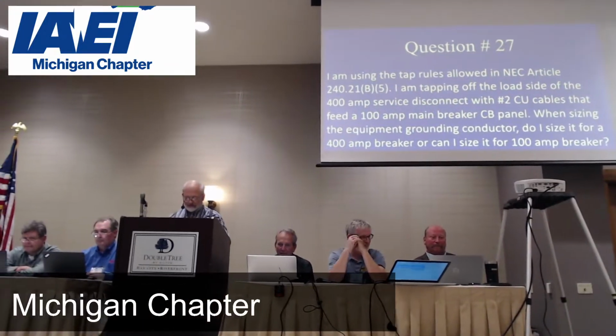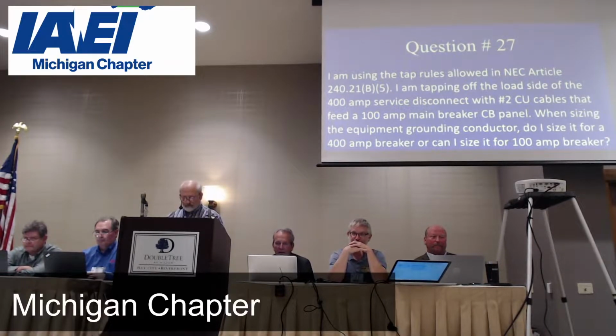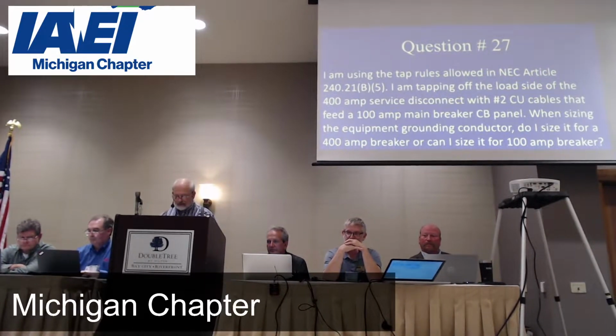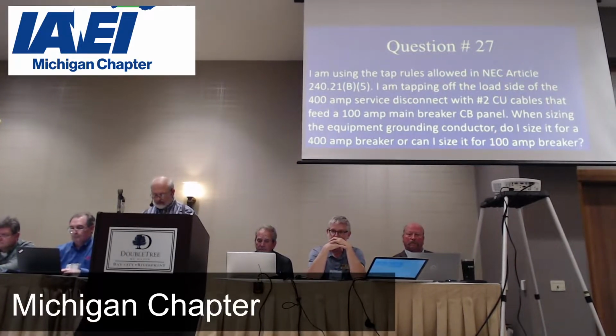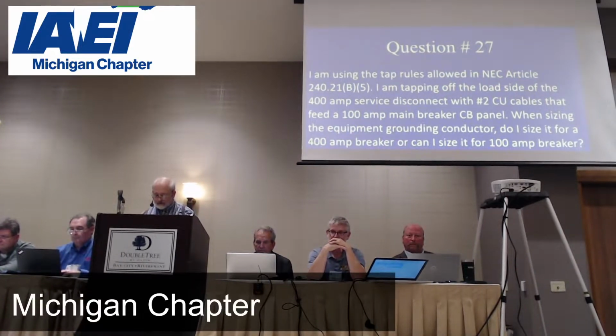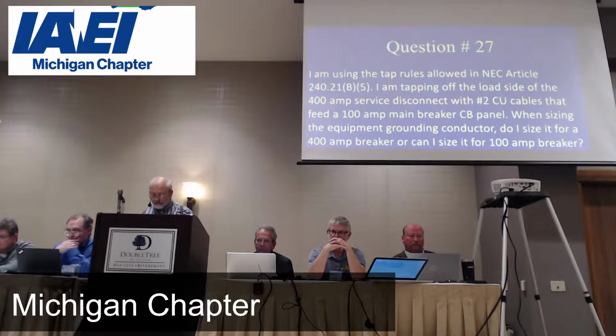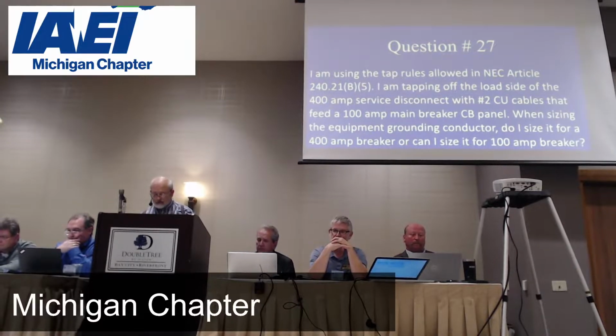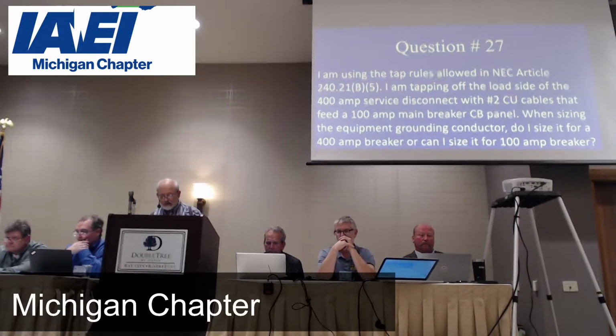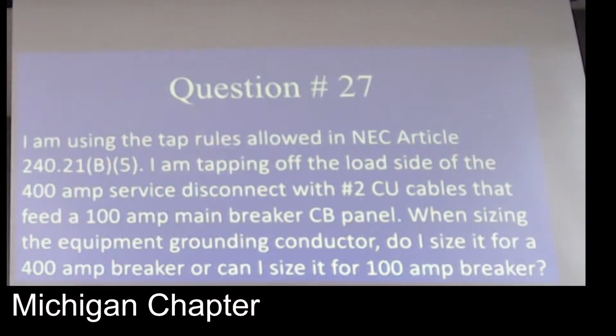Okay, 27, go. I'm using the tap rules allowed in NEC Article 240.21(B)(5). I'm tapping off the load side of a 400 amp service disconnect with number 2 copper cables that feed a 100 amp main circuit breaker. When sizing the equipment grounding conductor, do I size it for the 400 amp breaker or do I size it for the 100 amp breaker?